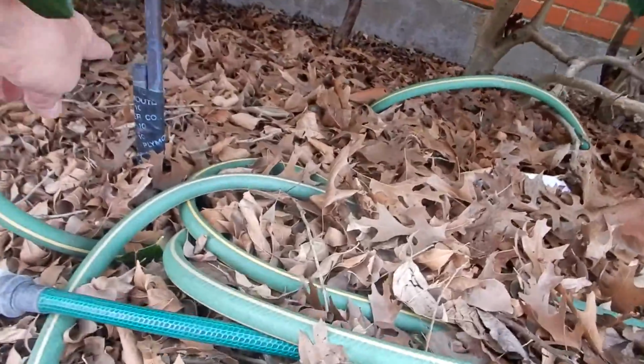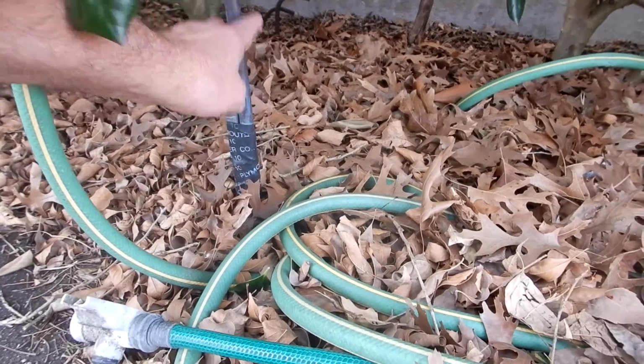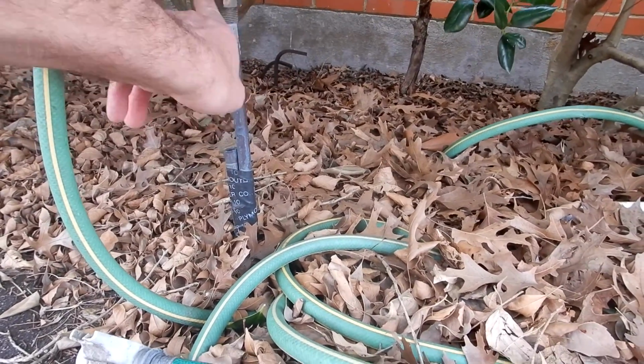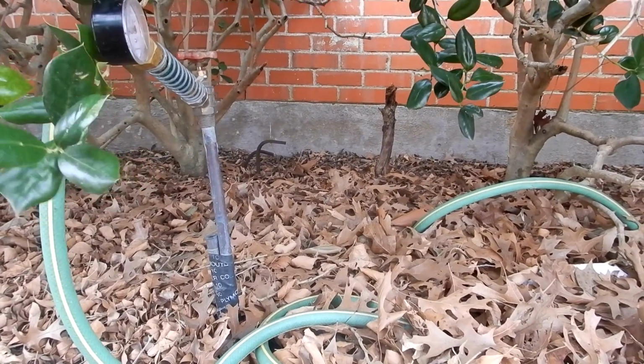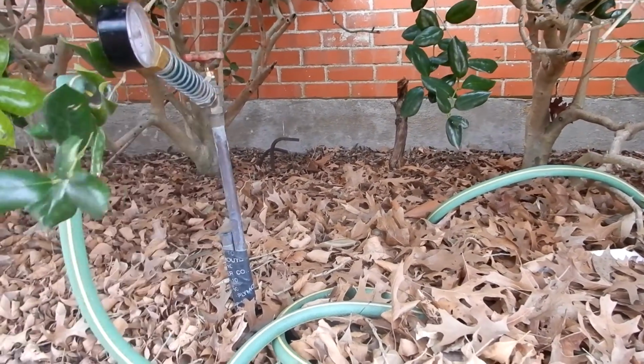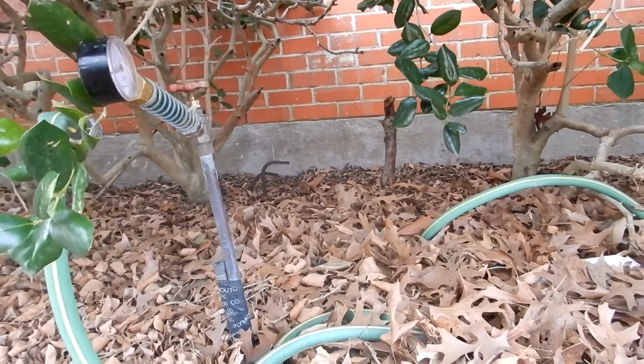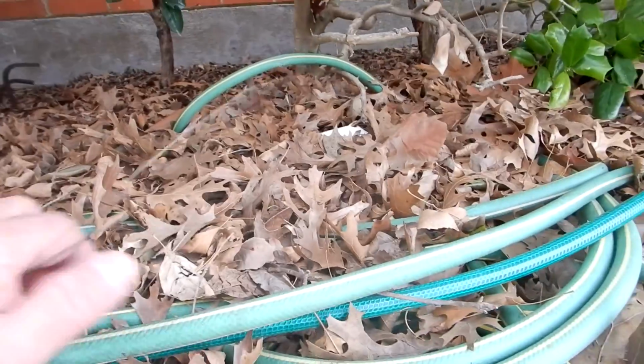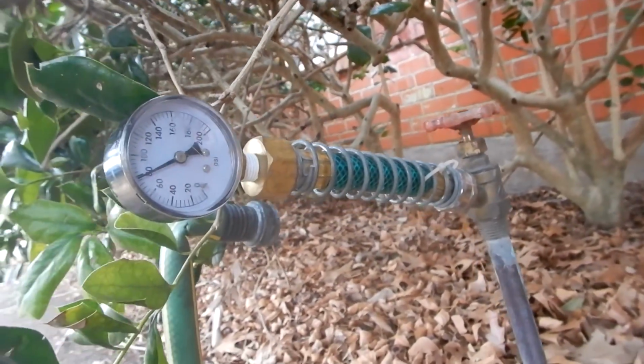This valve is supported, which is good. This piping should be insulated, and we do not have a vacuum breaker for potable water. I mean, to keep water pressure from going backwards into your potable, your drinking water. So let's go back over here. We've waited a couple minutes, and yep, we're still looking at 79 psi. So that's that.